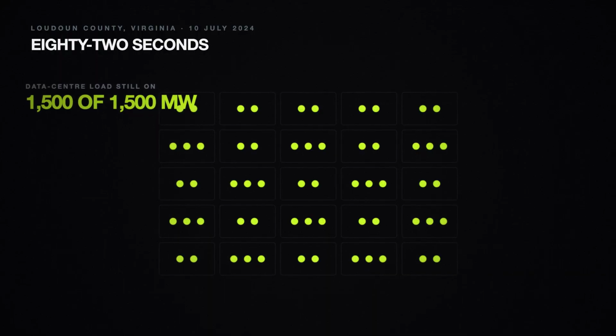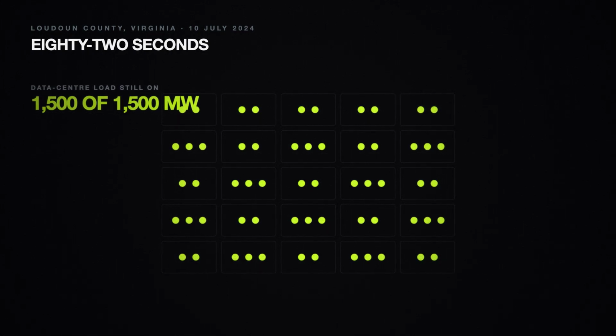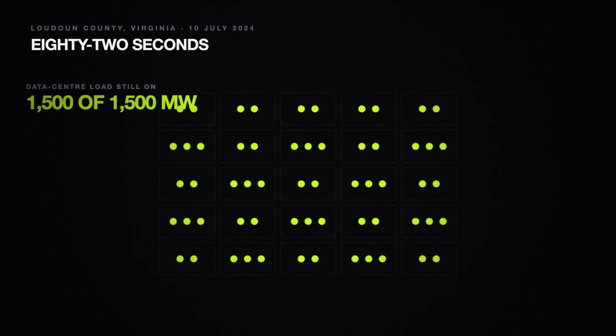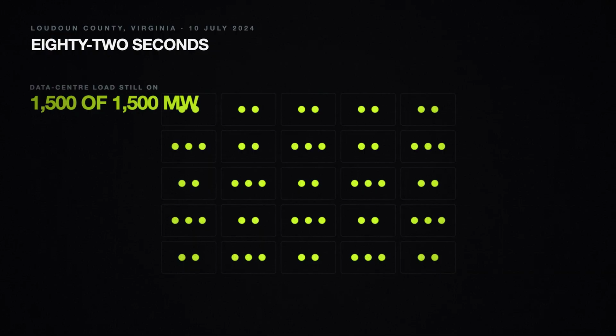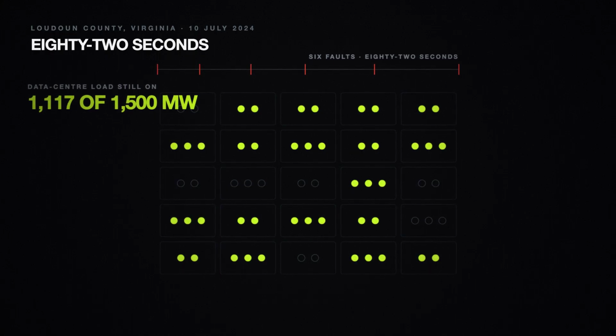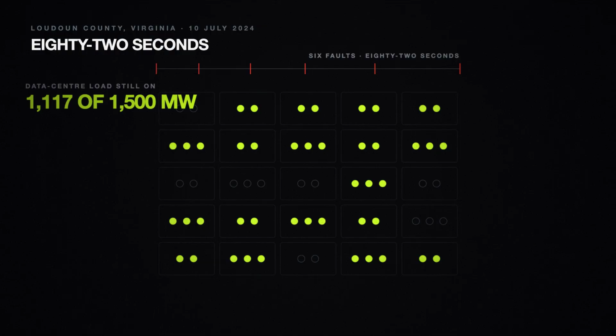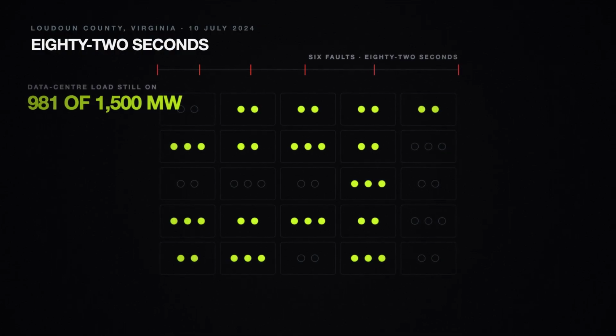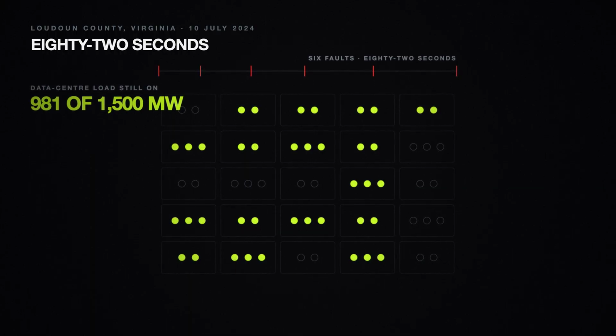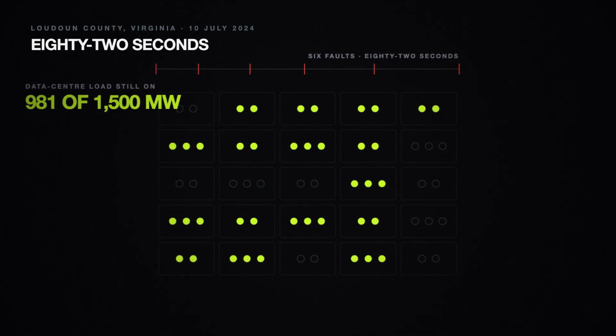It opened the line. Then, because most faults on overhead lines are temporary, a branch, a bird, a flashover that clears itself, it closed the line again to find out whether the fault was still there. It was, so it opened again and closed again. Both ends of that line were set to try 3 times, and the timers at each end were staggered. What should have been 1 fault became 6, spread across 82 seconds. Every one of those 6 was cleared correctly in 42 to 66 thousandths of a second. Nothing broke, nothing was damaged, no operator made a mistake.